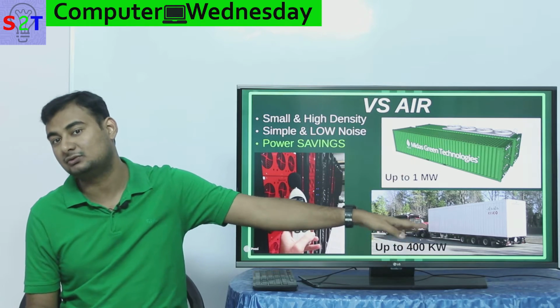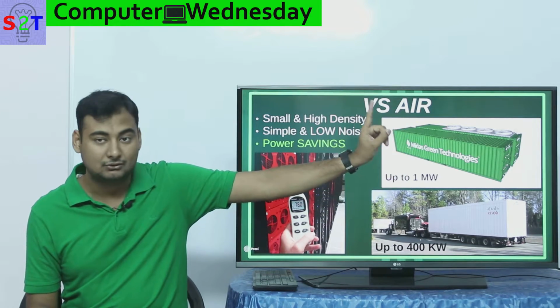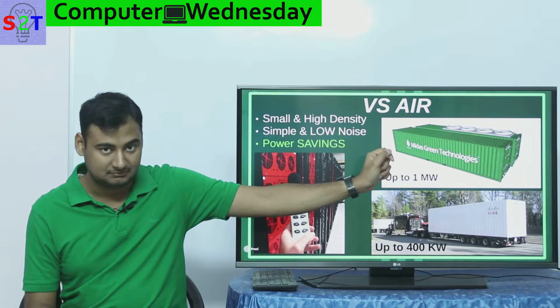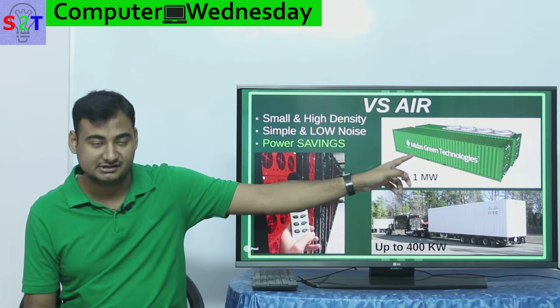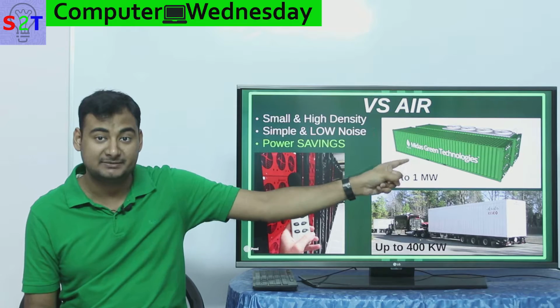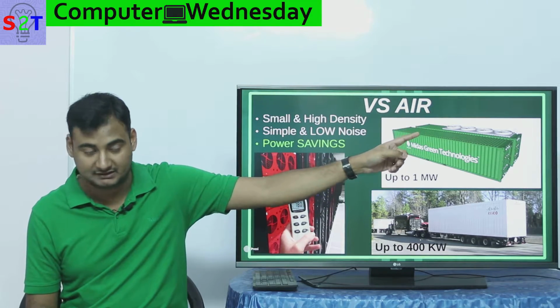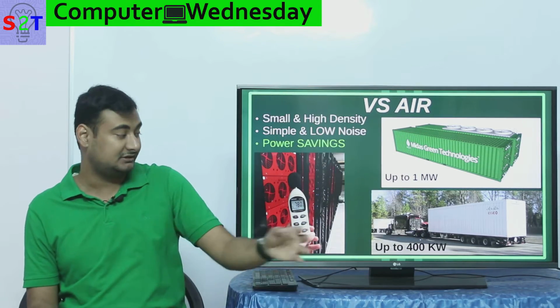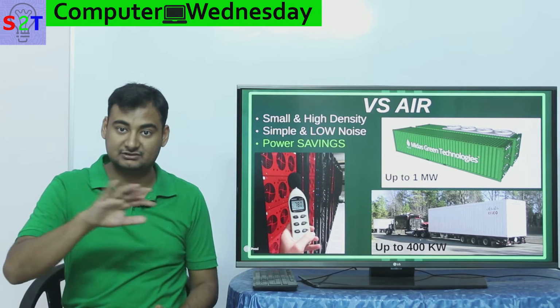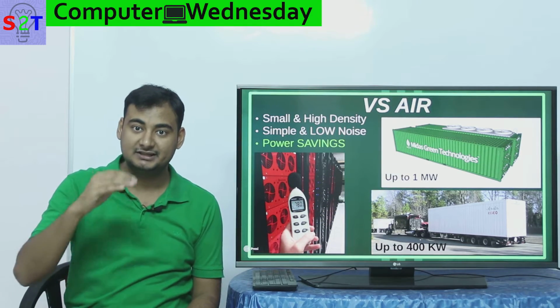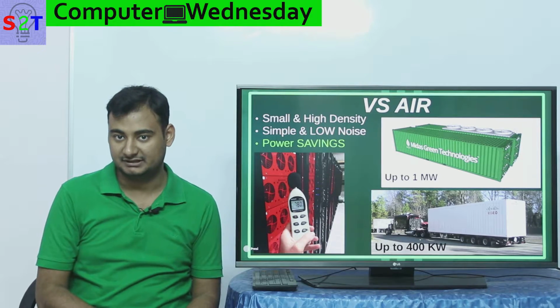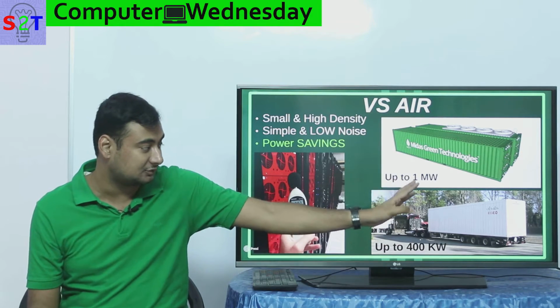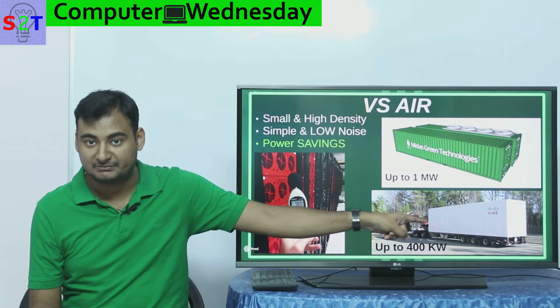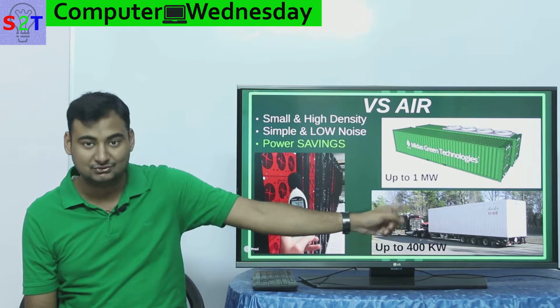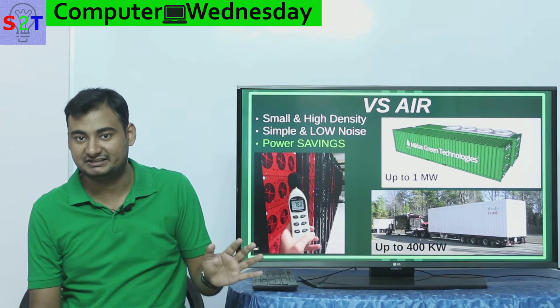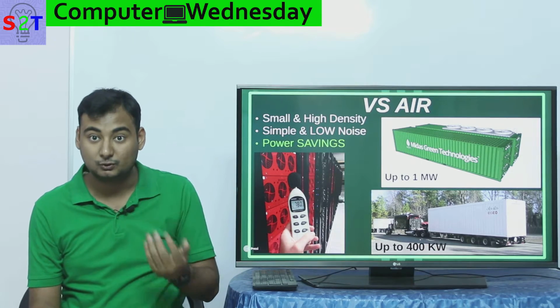Of course it has external cooling and all that, but I've provided the link down below — this one is an oil-cooled system that can handle upwards of 1 megawatt, also with an external cooling solution. As you can see, even though the cooling solution in both scenarios is separate and handled elsewhere, there is still a huge gap, because if you tried to cool this down with air while dumping 1 megawatt of electrical energy here, you'd have to cool the air down to something like minus 80 degrees Celsius just to extract the heat quickly enough.